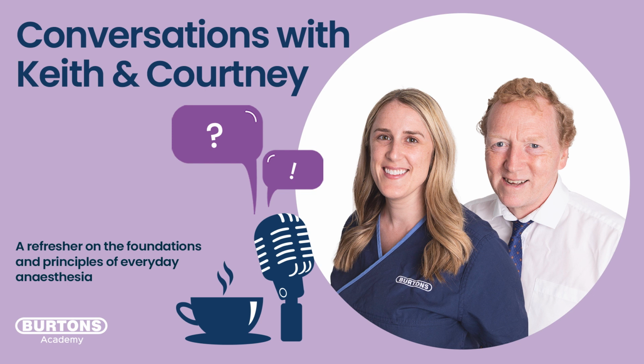Mm-hmm. I just want to qualify whether we can really start to believe it. I'm going to go back to something you just said very briefly. You said it has to be the right arterial sampling line, and I want to stress how important that is. If you're using anything other than a dedicated arterial sampling line, you're really going to upset the way that waveform is presented. If you've ever had anything to do with invasive blood pressure, you'll have heard the terms damping: there's critical damping, over damping, and under damping. I don't want to get too involved in the physics of it, but it is important to understand those terms, because if you have either over damping or under damping, it's really going to seriously affect not only the outline of your waveforms, but also the numbers that you get.